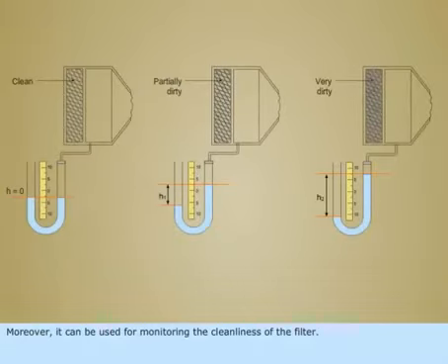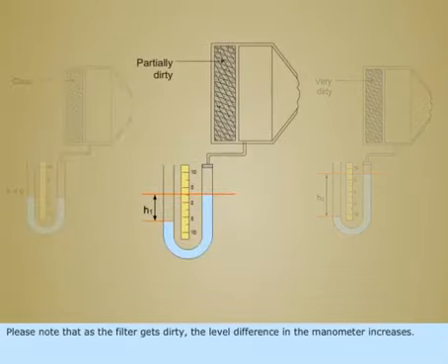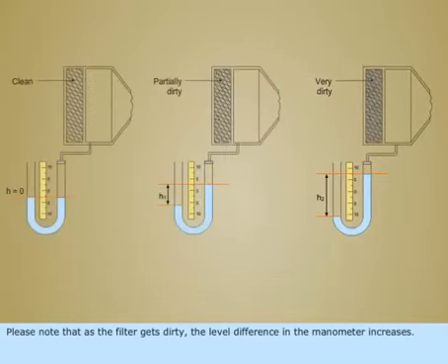Moreover, it can be used for monitoring the cleanliness of the filter. Please note that as the filter gets dirty, the level difference in the manometer increases.